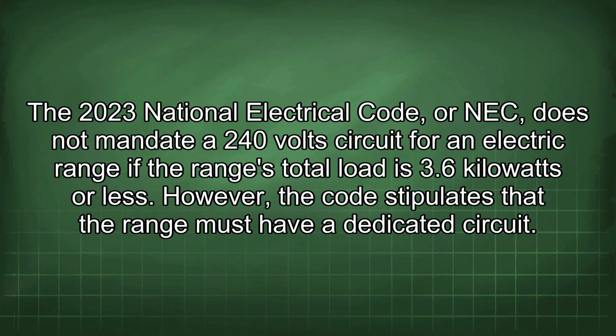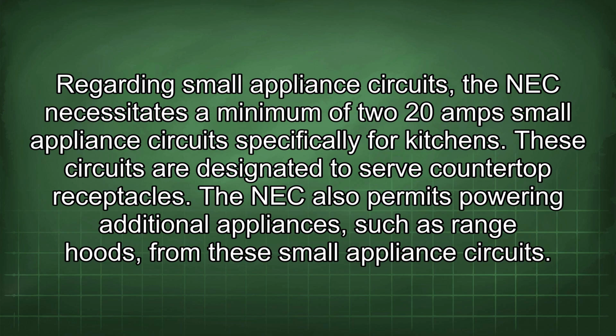The 2023 National Electrical Code, or NEC, does not mandate a 240-volt circuit for an electric range if the range's total load is 3.6 kilowatts or less. However, the code stipulates that the range must have a dedicated circuit. Regarding small appliance circuits, the NEC necessitates a minimum of two 20-amp small appliance circuits specifically for kitchens. These circuits are designated to serve countertop receptacles.